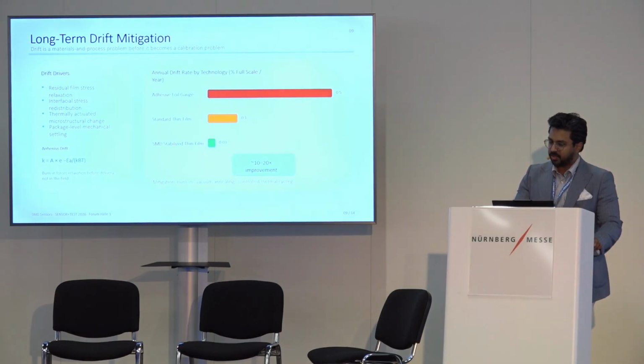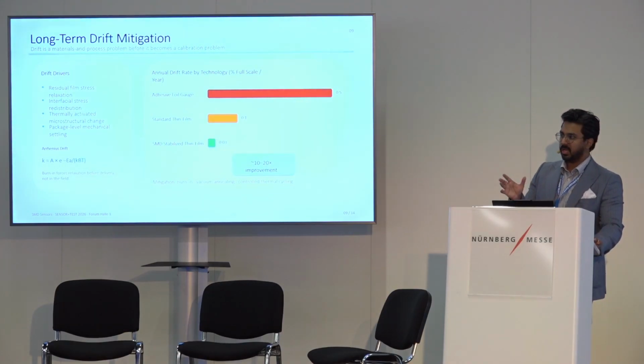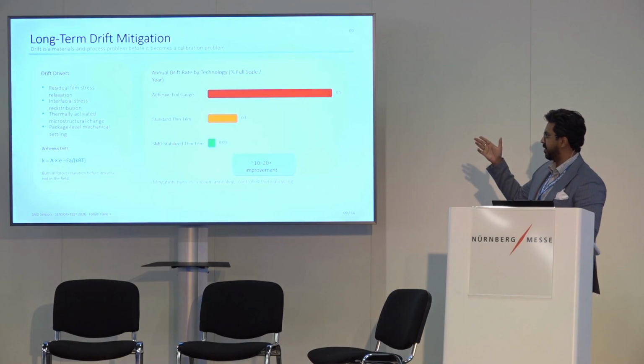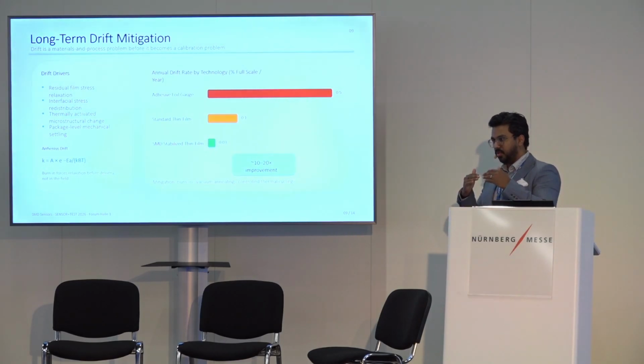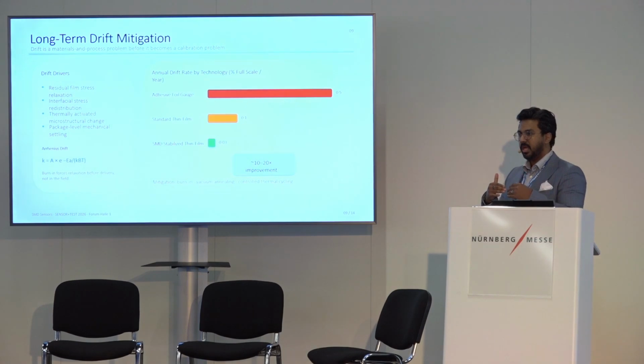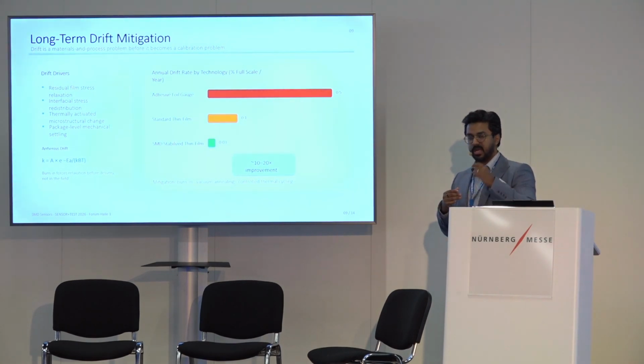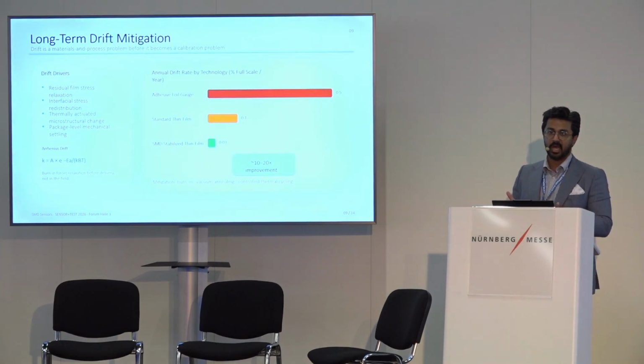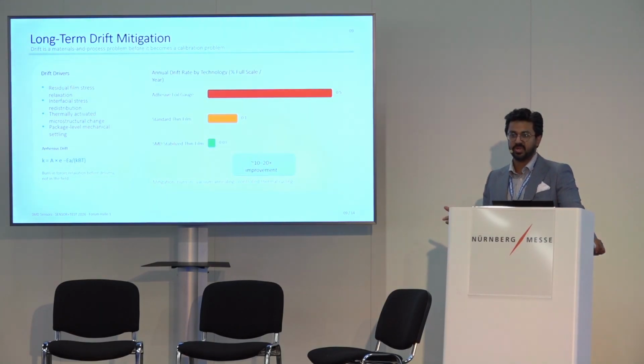The chart on the right shows the result of these drift drivers and the optimization after we perform it. So let me give you an example of how one of these drift drivers works. For example, the residual film stress. When we do thin film on a substrate, following my previous slide, if the thermal coefficients don't match, it creates a stress and strain on the substrate, which we call the phantom strain. And that is usually not looked into in calibration until you are looking for extremely high resolution. And think about high temperature applications, where you're looking at high resolution at high temperature and at a certain pressure range that you want to validate.